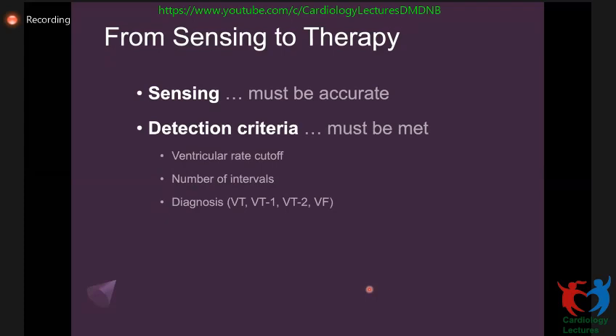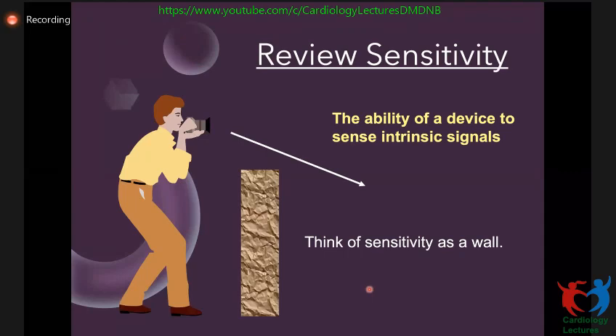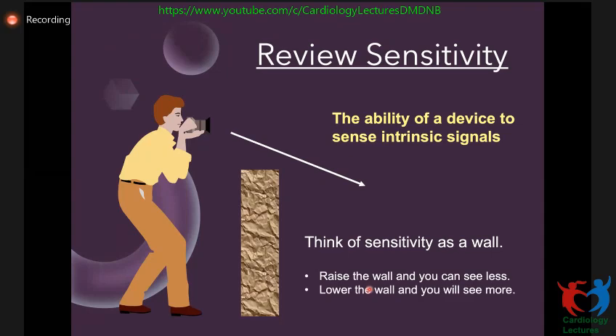For the ICD, it has to have very accurate sensing, good detection criteria to diagnose VT or VF, and good discrimination between VT and SVT to give therapies appropriately. When talking about sensitivity, it's the ability of the device to sense intrinsic signals — like being on one side of a wall. If you raise the wall too high, you see less; if you lower it, you see more.